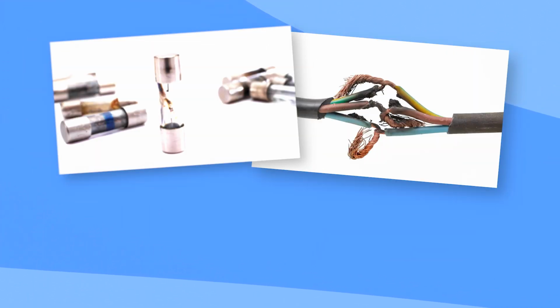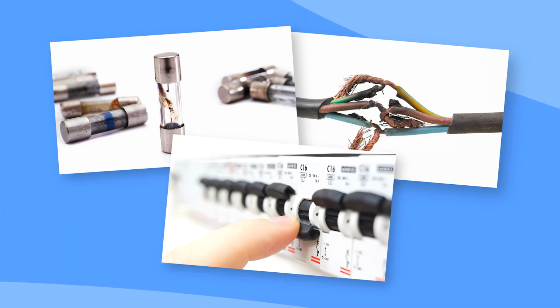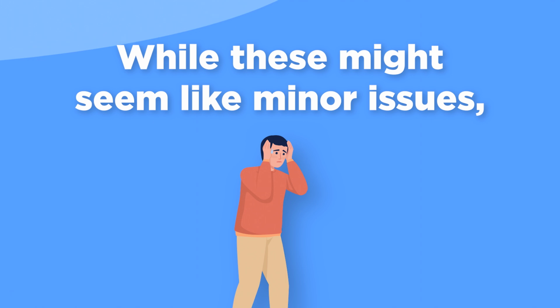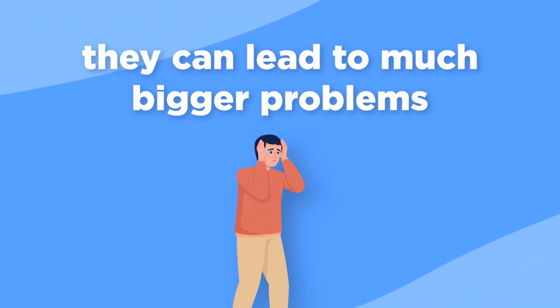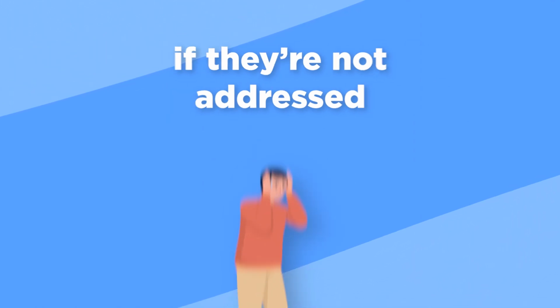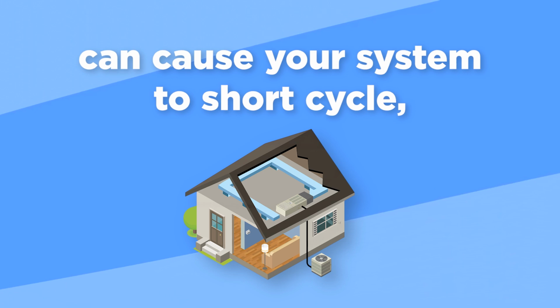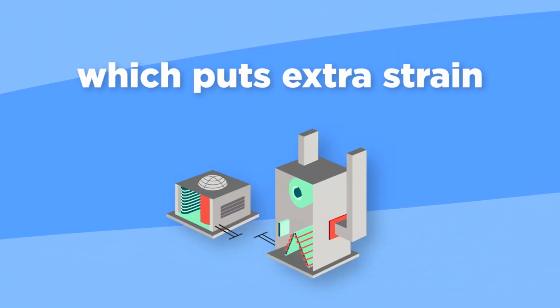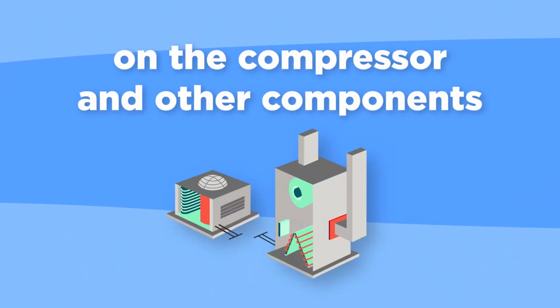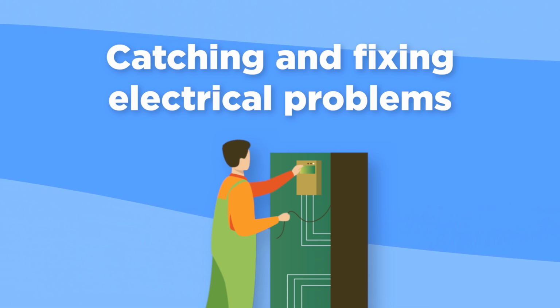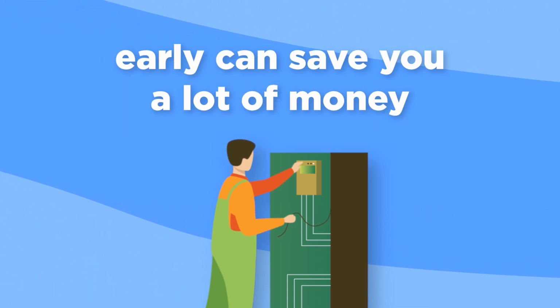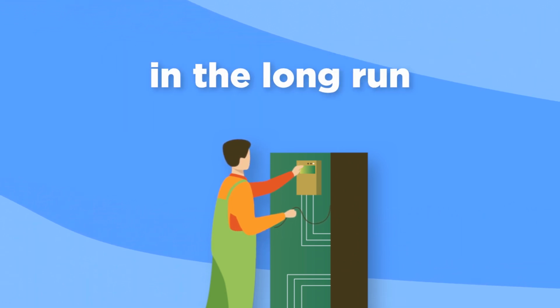Faulty wiring, blown fuses, or tripped breakers can all cause your HVAC system to stop working. While these might seem like minor issues, they can lead to much bigger problems if they're not addressed. For instance, electrical issues can cause your system to short cycle, which puts extra strain on the compressor and other components. Catching and fixing electrical problems early can save you a lot of money in the long run.